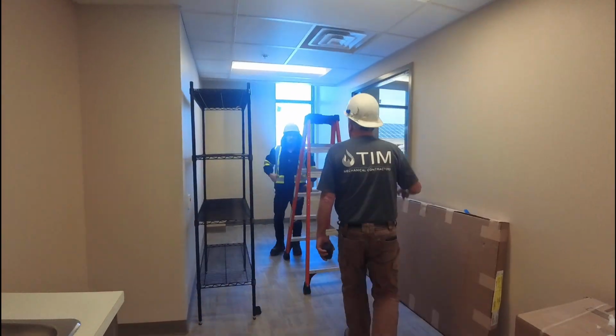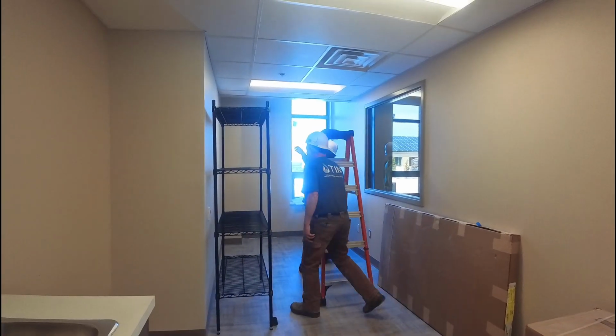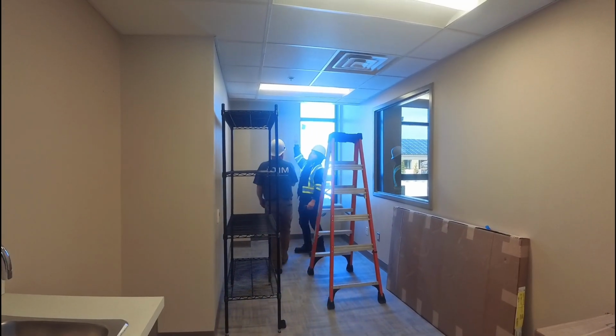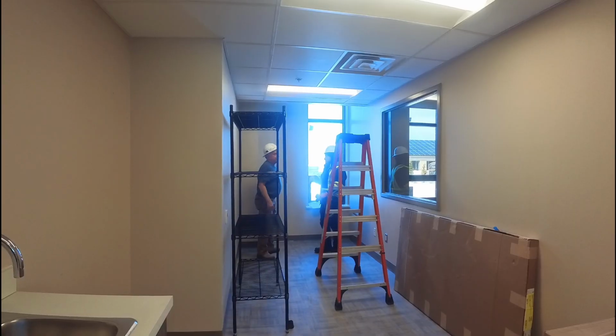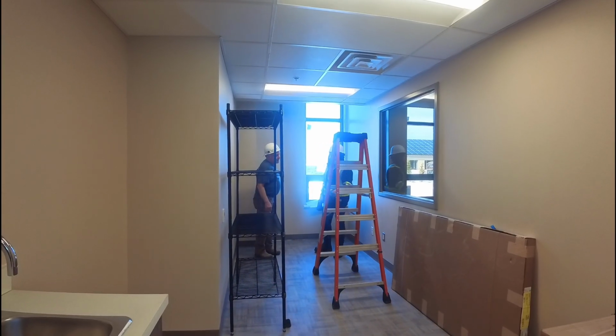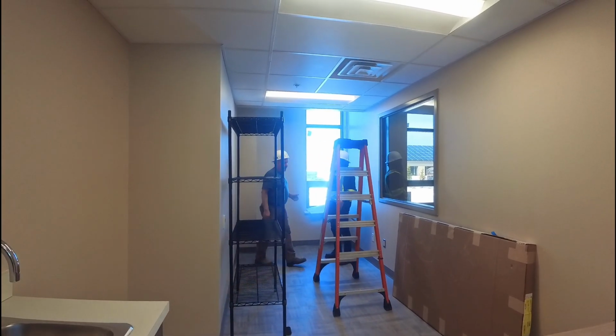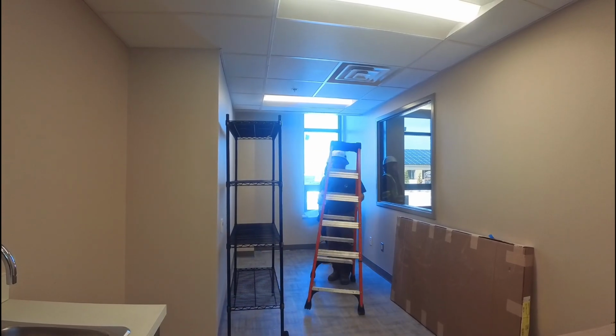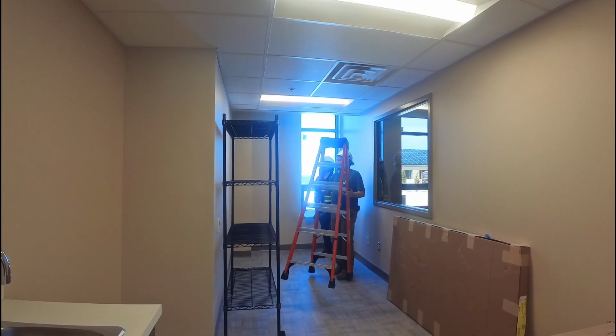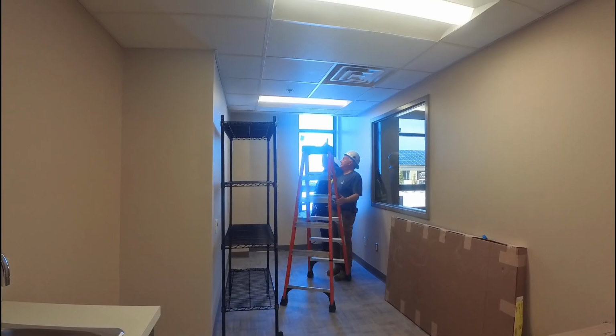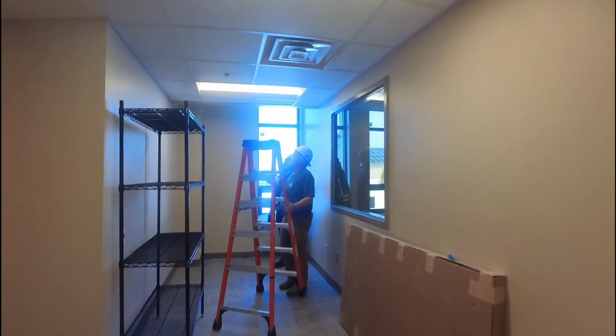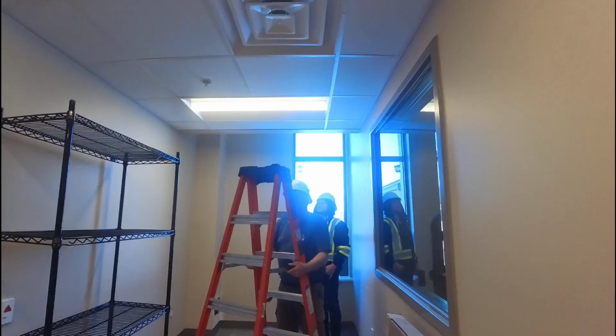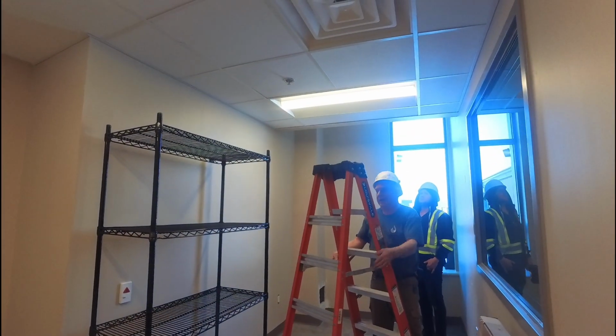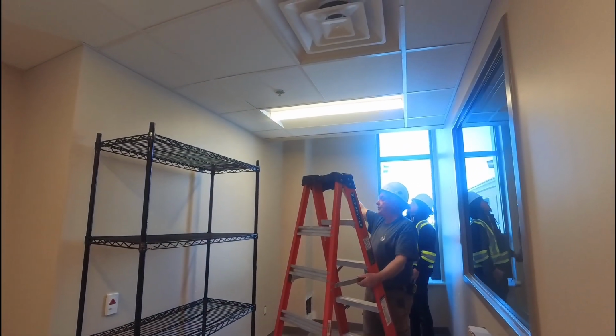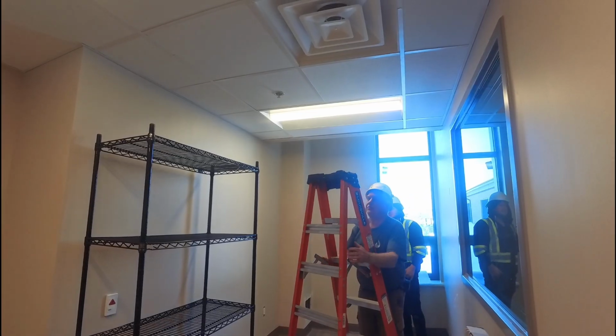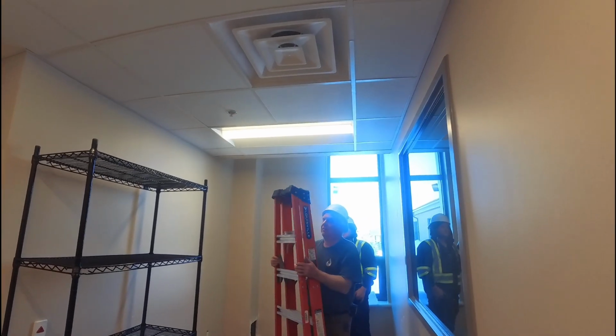Coming out too much here? Well, yeah, that's supposed to be pulling air out of the room. It's supposed to be pulling out and mixing in fresh air. What's going on? The bypass damper is wide open. It's supposed to be supplying air to the plenum on the return side of it, right? Yeah. So it's not calling. This thing's not asking for any air, and it's getting all blown out there. So the bypass damper hasn't been, and this is kind of confusing to me. This has all been pre-balanced.